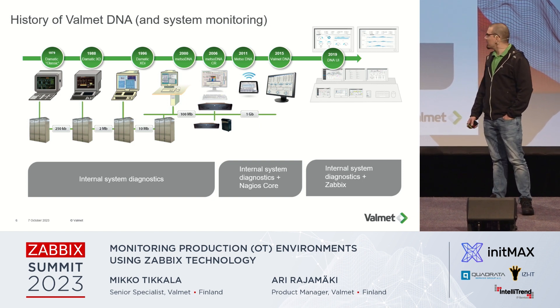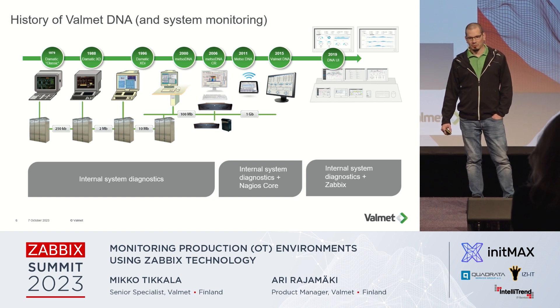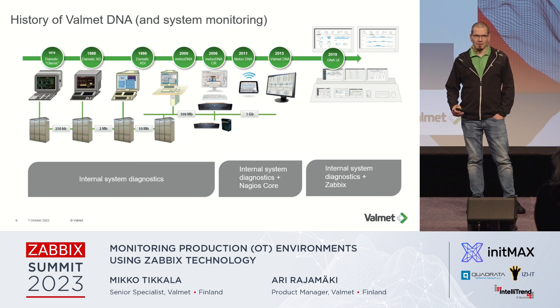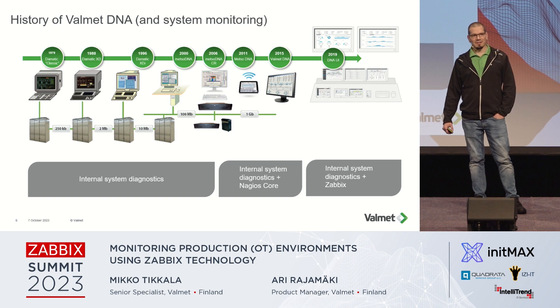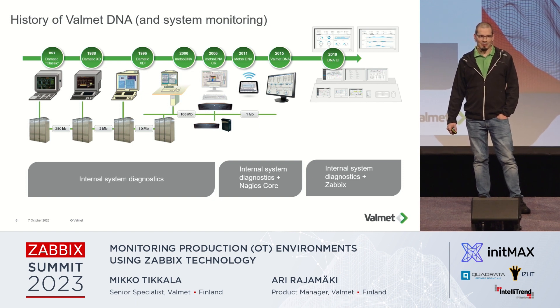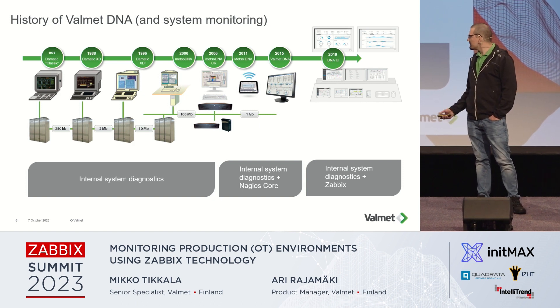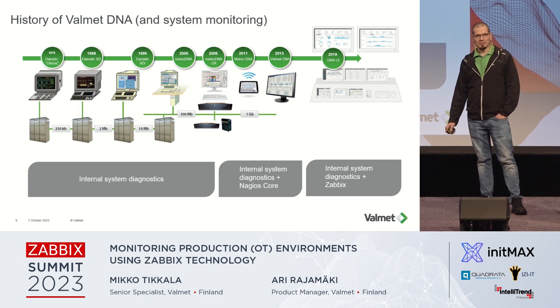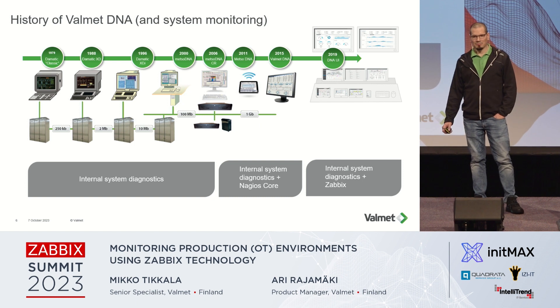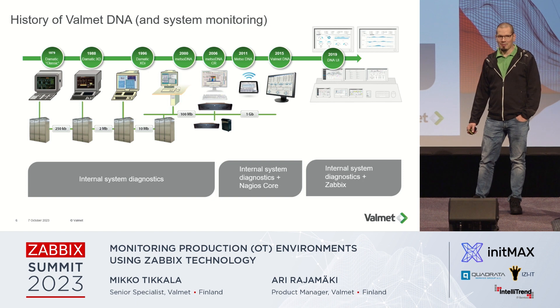Then some group of people found out that maybe they could use some software to extend this internal system diagnostics, and they selected Nagios. But after a few years of running that, we found the need for a more powerful and more flexible monitoring system, so we ended up with Zabbix. It's quite normal for control systems to be running in the plant for very long times — maybe even 40 years — which sets some limits to monitoring, because there could be really old devices with poor CPUs or small amounts of memory. So we cannot overload the system by monitoring.